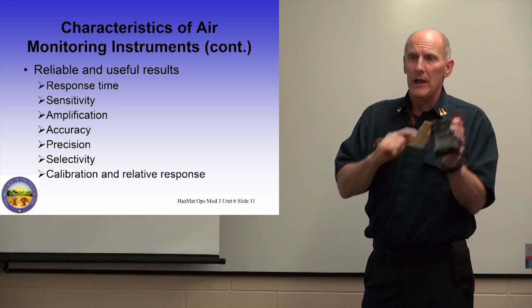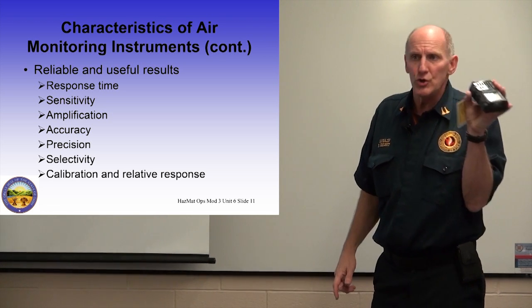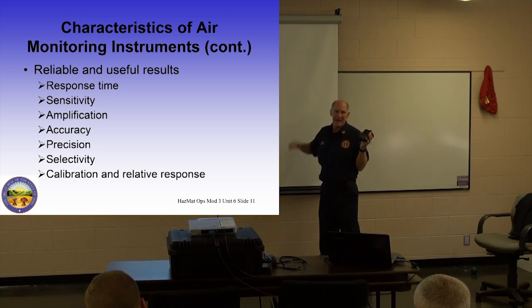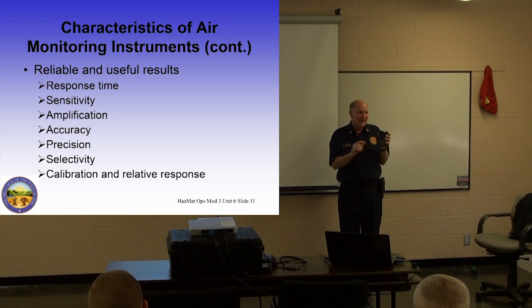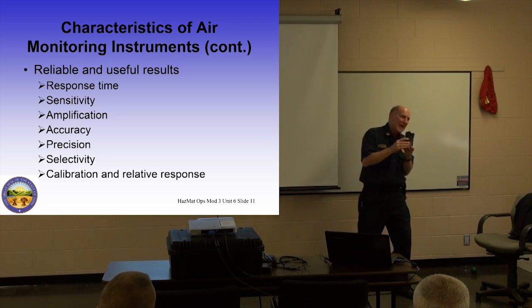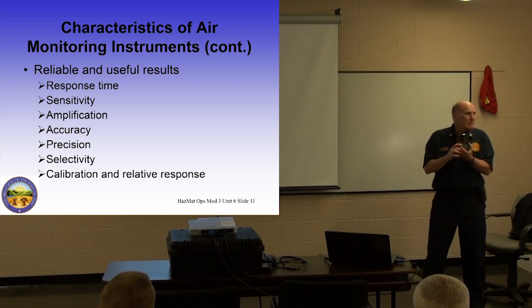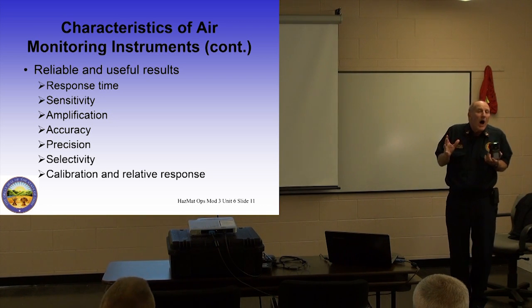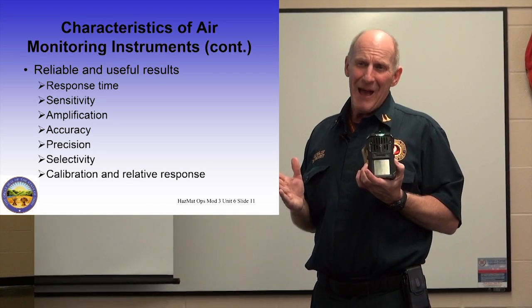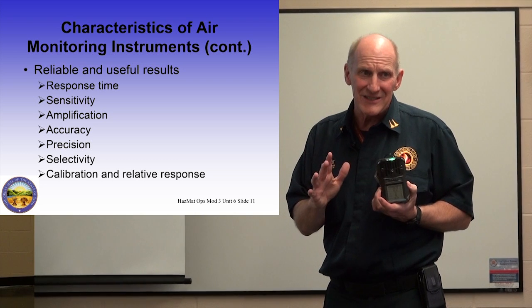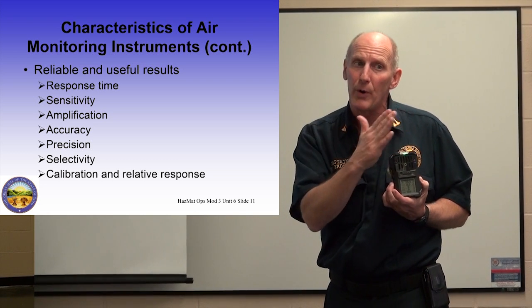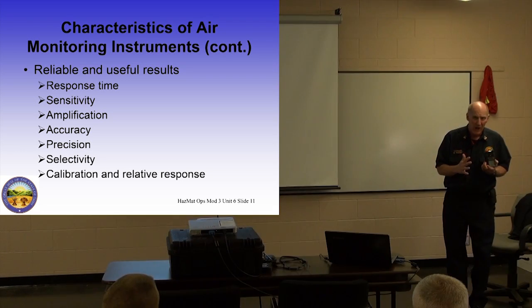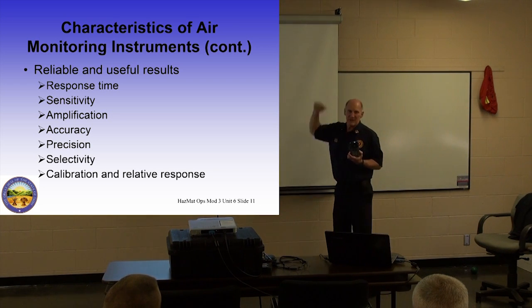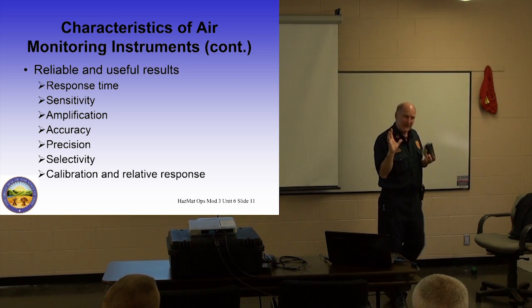And it may not be readable any other way. So you cannot trust the O2 meter as being sensitive. The LEL meter is the same way. The LEL meter reads a percent of a percent, and that means it's a little bit more sensitive. It's going to drop to 100 parts per million before it makes a change. But again, what I have to understand is that sensitivity isn't there.